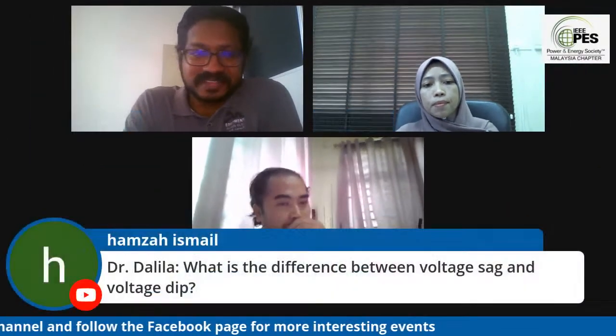Of course, in the real measurement, it will not be 100% the same measurement from the PMU and the measurement using KCL and KVL. That is why we propose to use the negative sequence for location and cannot use a number of PMUs that is too small. So we just need to optimize the number of PMUs. So insha'Allah, maybe in future we can pick up this problem for using unsynchronized measurement when there is a signal loss. I hope I can answer. Thanks. Thank you, Dr. Rafi. We could go to the next question.